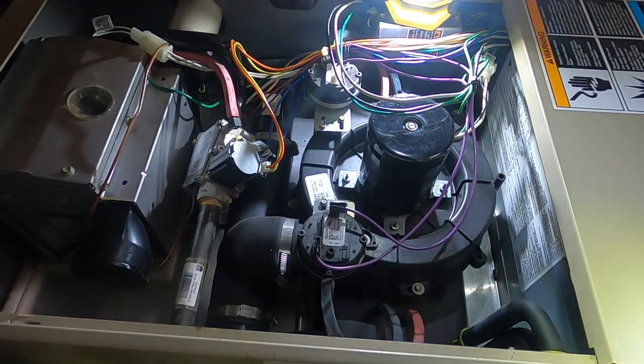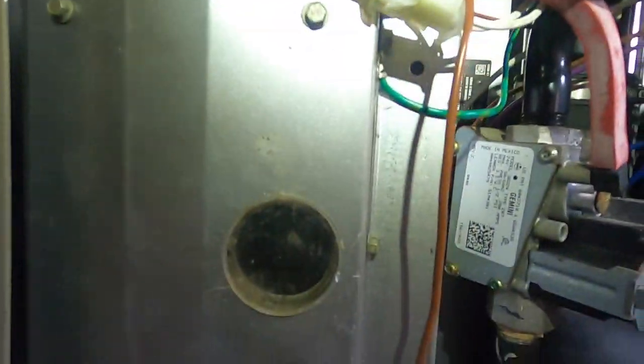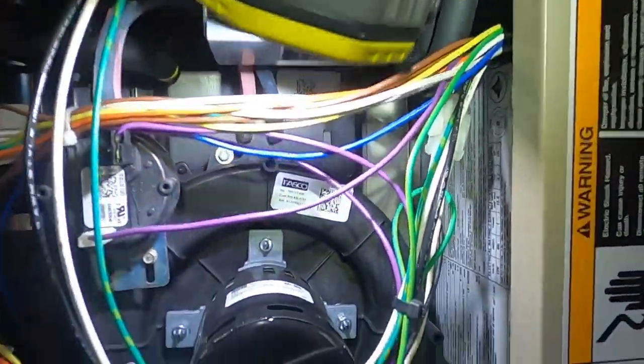All right, so I've done about as good a visual inspection on the heat exchanger as I can, going back inside the burners, going back in through the coil. Like I said, pulling the blower out of this thing, it's a 90% furnace, so your secondary coil is going to be right in the way. Nothing in here is rusted over time. What is the year model on this? How old is this thing actually?